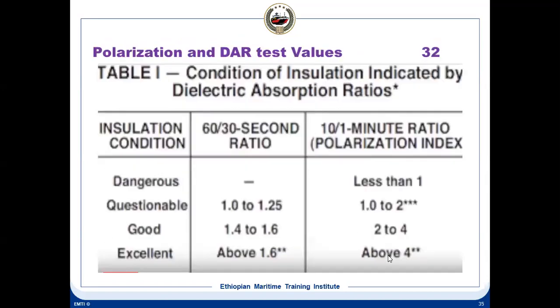But for the PI test, you see your PI values. That means you apply a Megger for 10 minutes, take the reading, and divide it by the 1 minute reading. You divide it, let's say 100 by 90. What you get is this figure, that is 1.0 to 2.